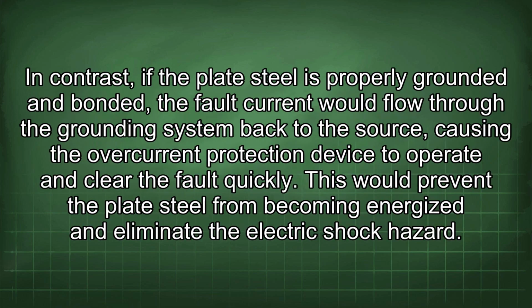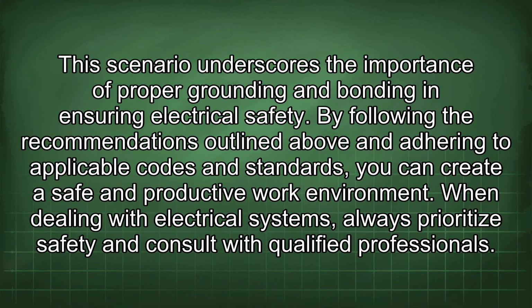In contrast, if the plate steel is properly grounded and bonded, the fault current would flow through the grounding system back to the source, causing the overcurrent protection device to operate and clear the fault quickly. This would prevent the plate steel from becoming energized and eliminate the electric shock hazard. This scenario underscores the importance of proper grounding and bonding in ensuring electrical safety.